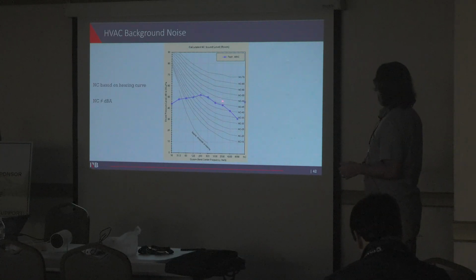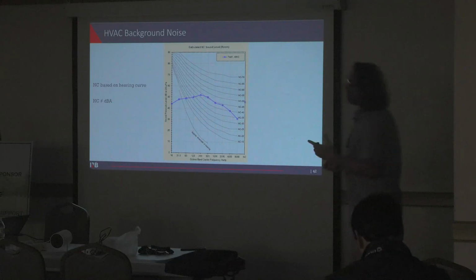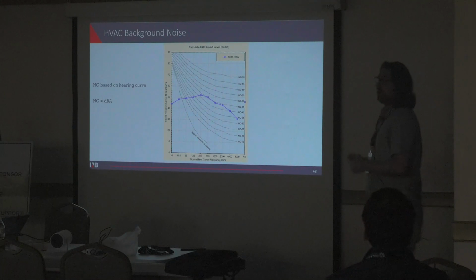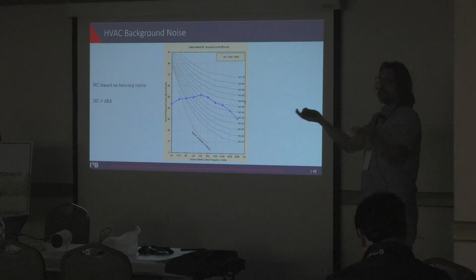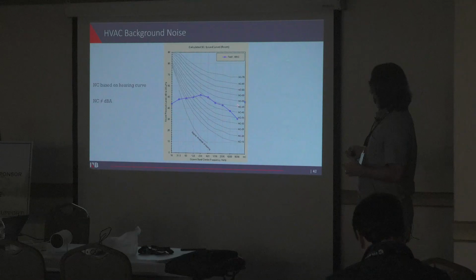So here's our NC45, right? The highest curve that we break is this NC45 curve right here. We break it by about a point, so that's an NC46. Now, what's important about this, and we're going to update this slide afterwards, I wish it was on here already, is just like I said before about STC50, STC50 doesn't necessarily mean the same thing. That's the same thing with the NC. This is driven completely by this one point right here. If we had another system that swooped all the way down here and looked completely different, they would both be NC46 because it's all driven just based on that highest point.